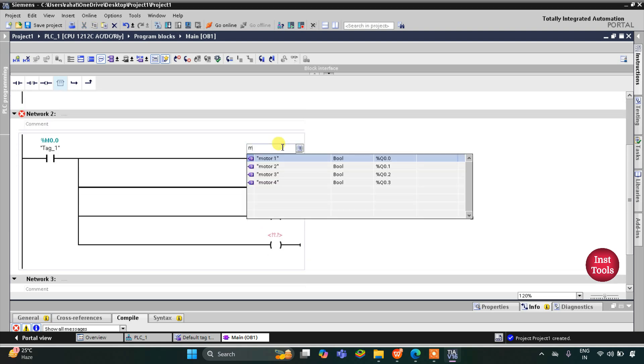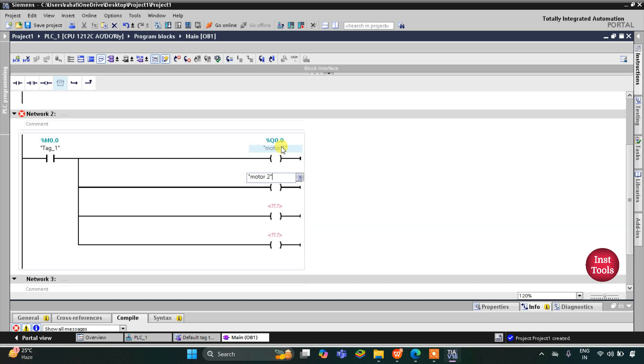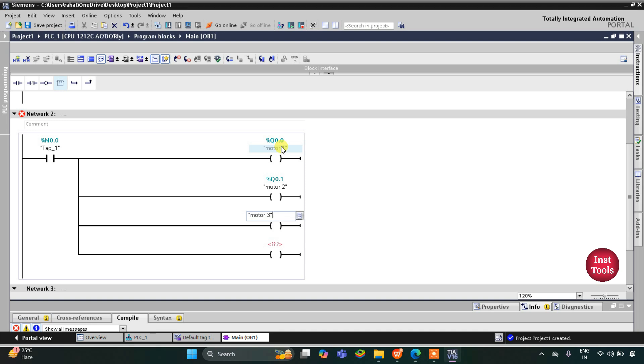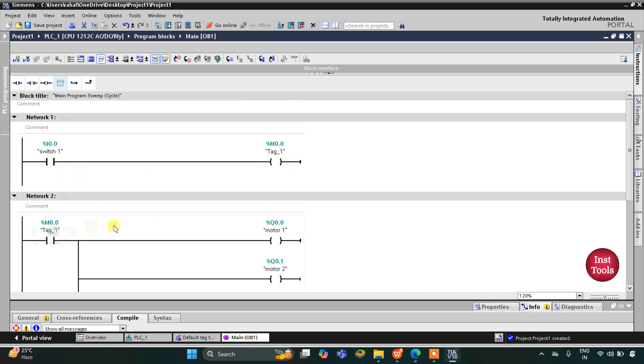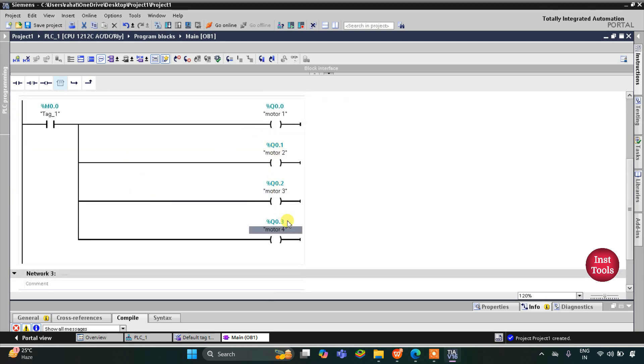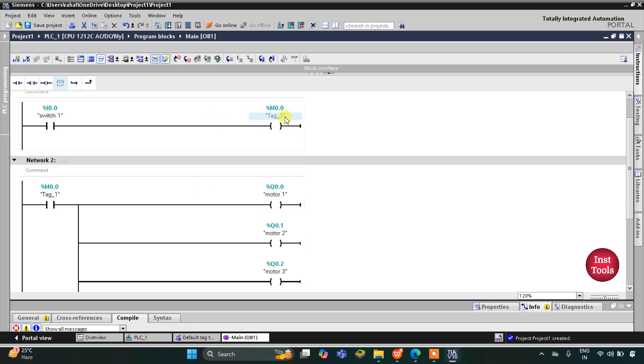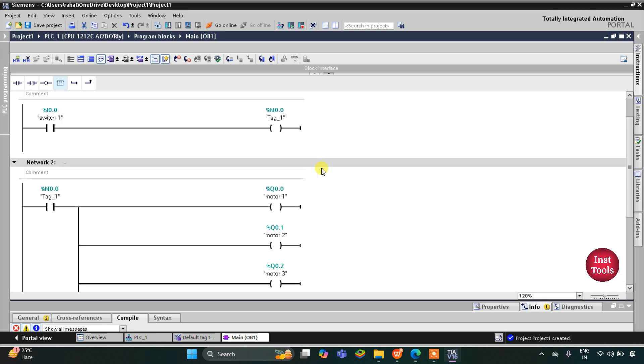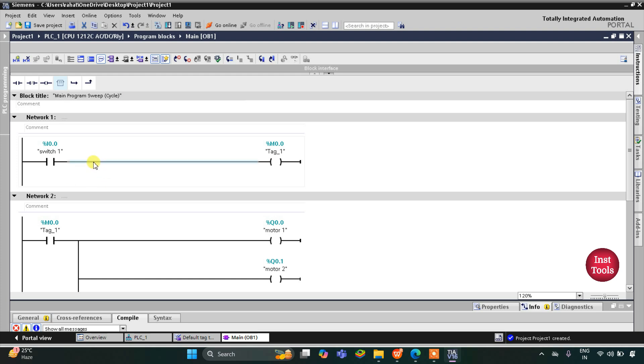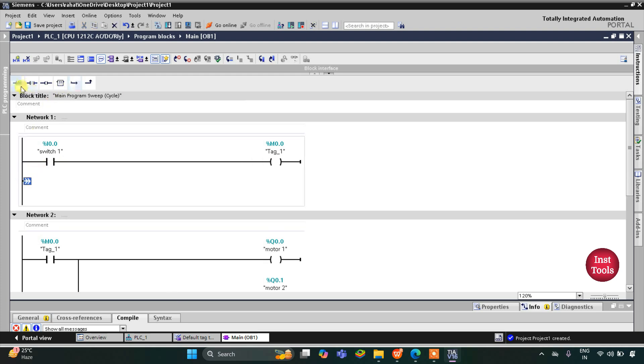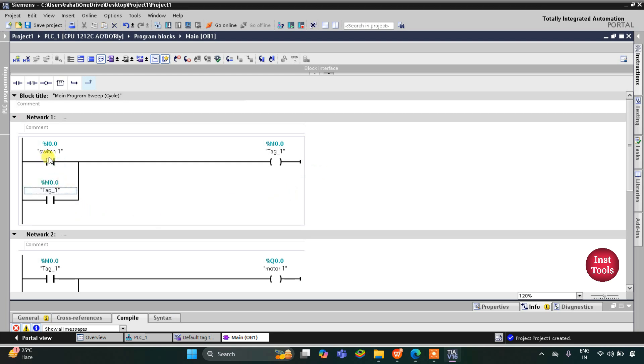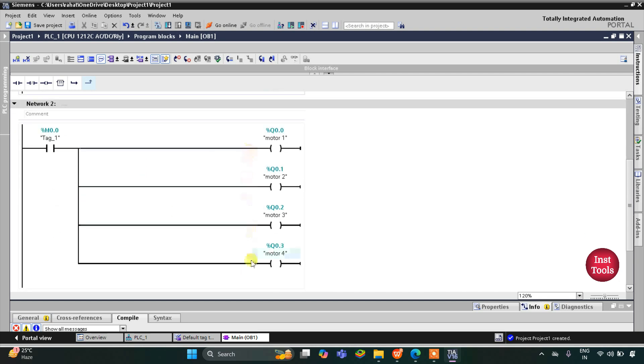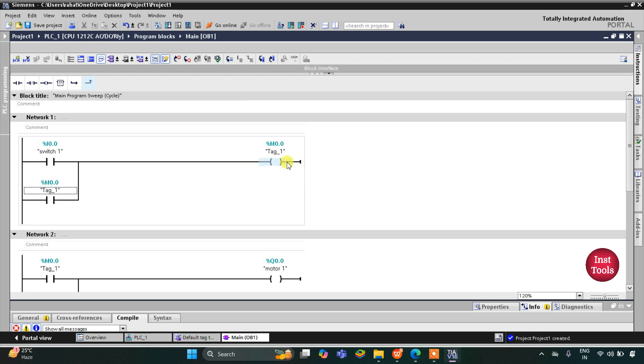These coils will be motor one, motor two, motor three, and motor four. When switch one is turned on, M0.0 gets true and as a result motor one, motor two, motor three, and motor four turn on. But when switch one is turned off, M0.0 gets off and as a result motors also get off. However, motors should remain on when switch one is turned off, so here we will implement latching. I will open a branch and add a normally open contact with address M0.0 — so we have latched M0.0. When switch one is turned on M0.0 gets true, and when switch one is turned off M0.0 still remains on due to latching, and as a result motors also remain on.